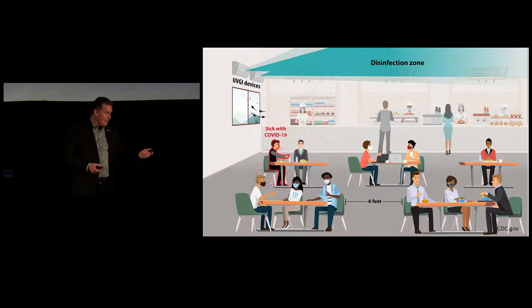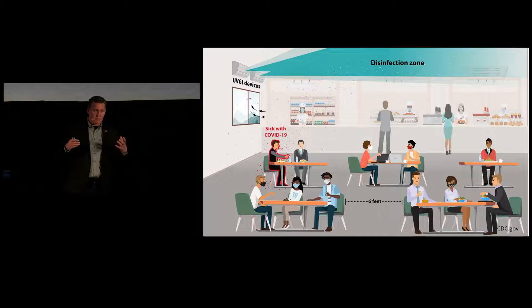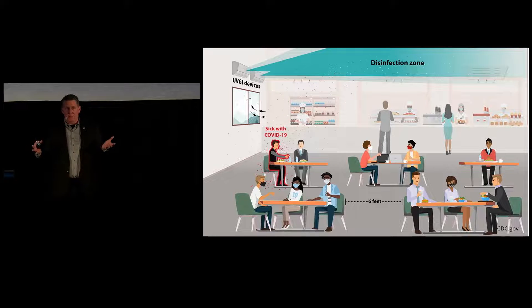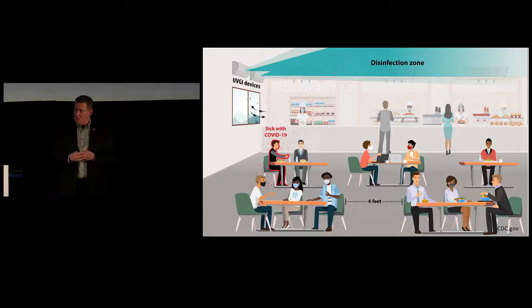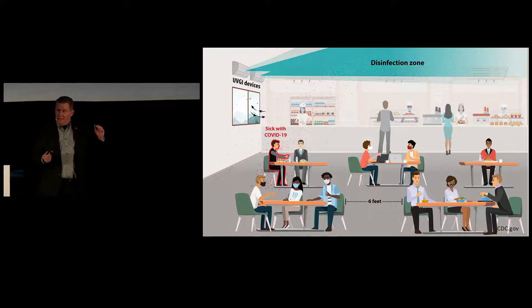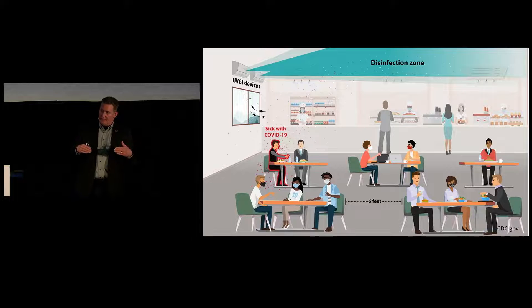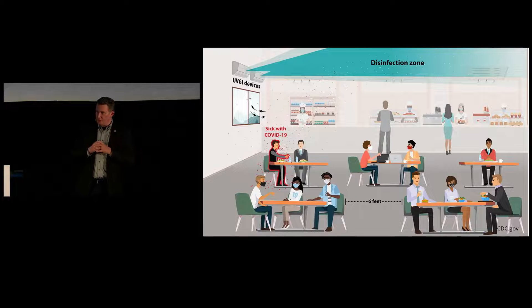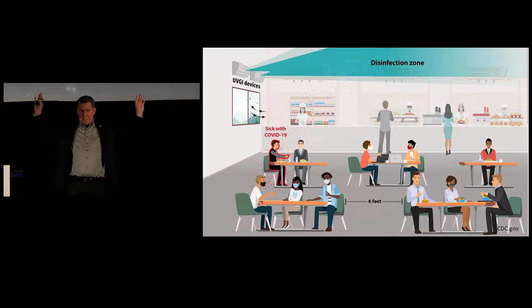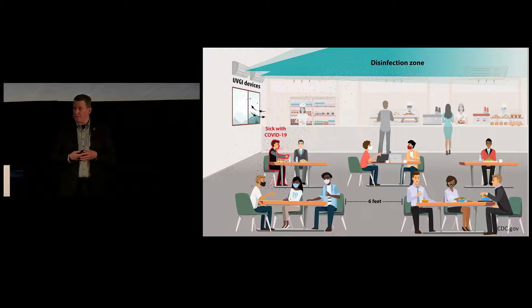Another common option is upper room UV. This slide is from the Centers for Disease Control. Basically, an upper room UV system — historically using 254nm — shines UV light horizontally over the tops of people's heads rather than directly exposing them. This is great because it doesn't matter what your HVAC capacity is; you're getting UV disinfection in the room where it's installed. If you think about a 10x10 room, you might have a tiny little grill providing fresh air into that space — you're trying to pump air through that tiny grill. But with upper room UV, the entire ceiling space becomes a disinfection zone, significantly increasing the amount of air that can easily flow through the disinfection zone and get disinfected.